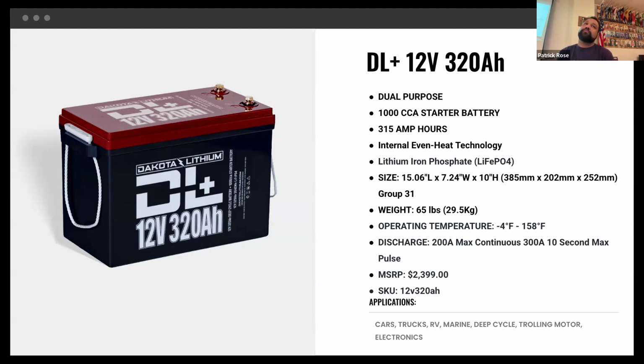Well, like on a car, the fuses are usually way smaller than the discharge capacity, are they not? I think part of the story is actually if you're going to use a very high current discharge rate to start a motor, you don't put a fuse between the battery and the motor. But you don't use that kind of battery in a domestic battery bank normally - then you put appropriate lower current discharge rate batteries in with fuses that are appropriate, the maximum you'd expect to get from each battery.